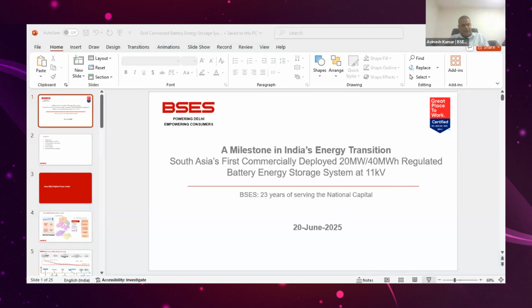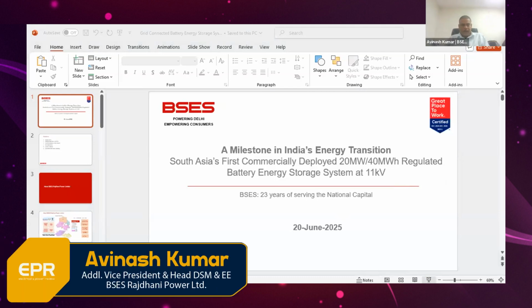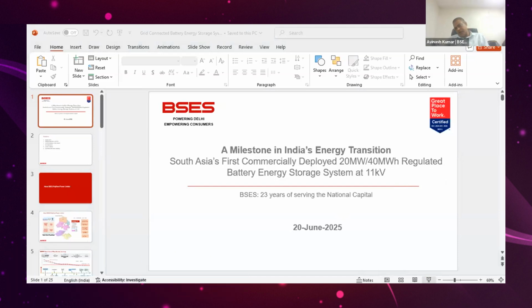Rajdhani Power Ltd has installed and commissioned South Asia's first commercially deployed 20 megawatt, 40 megawatt hour regulatory approved project at one of our grid substations, named Kilokri substation, at 11 kV level. Our consumer base is around 3.06 million, and we have 23 divisions in Southwest Delhi and 91 subdivisions.